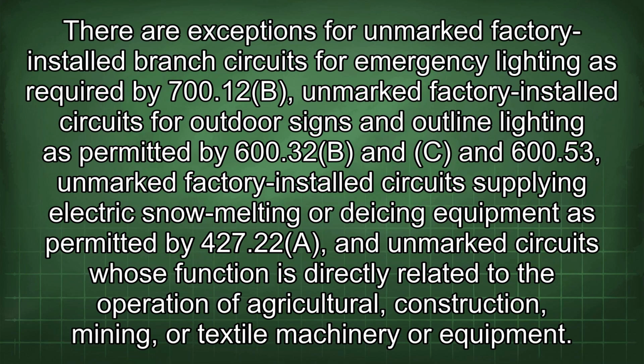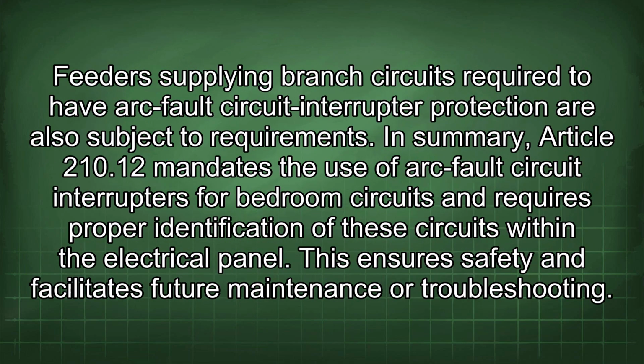There are exceptions for unmarked factory-installed branch circuits for emergency lighting as required by 700.12(B), unmarked factory-installed circuits for outdoor signs and outline lighting as permitted by 600.32(B) and (C) and 600.53, unmarked factory-installed circuits supplying electric snow melting or de-icing equipment as permitted by 427.22(A), and unmarked circuits whose function is directly related to the operation of agricultural, construction, mining, or textile machinery or equipment. Feeders supplying branch circuits required to have arc fault circuit interrupter protection are also subject to requirements.